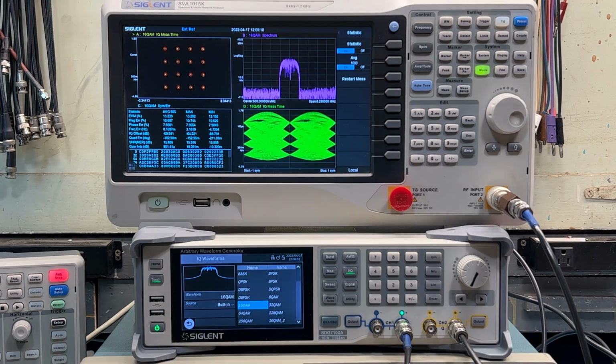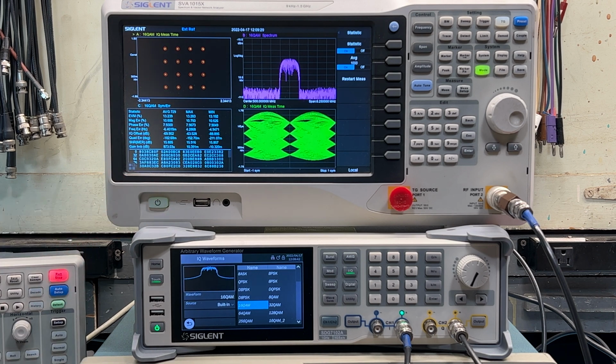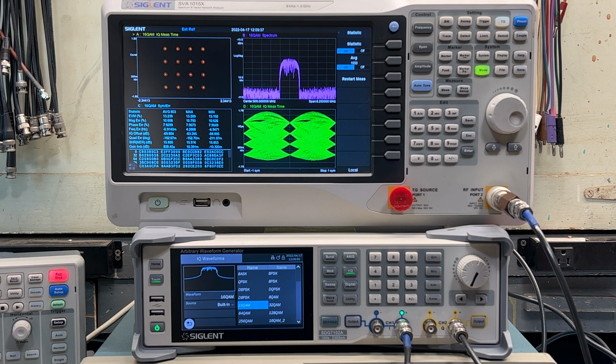Okay, so for the spectrum analyzer measurements I've been making, all of them except this one, I'm locking the spectrum analyzer to the clock in the SDG7102. This thing has an ovenized clock, and I have no reason to doubt that it's more accurate than anything else in my lab. I have nothing really to measure it with. I don't have a GPS reference or any other kind of standard frequency measurement. So I'm going to assume that they calibrated this correctly.